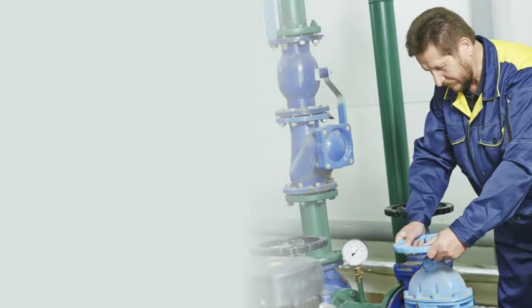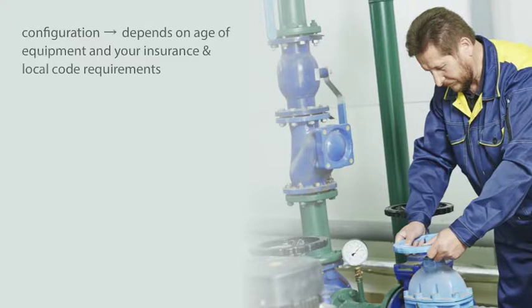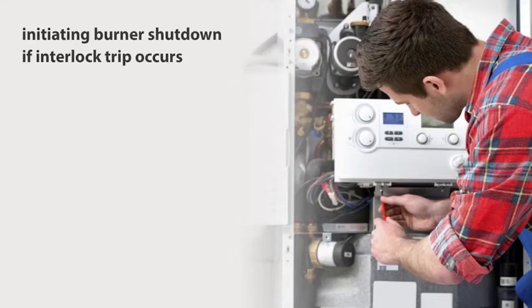Some small systems have only one automatic or actuated valve for this function. In other cases, and especially with boilers, double block and bleed systems are required. The specific configuration that your site has depends on the age of the equipment and your insurance and local code requirements.